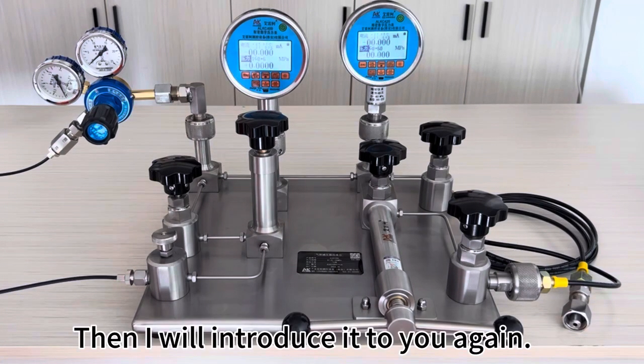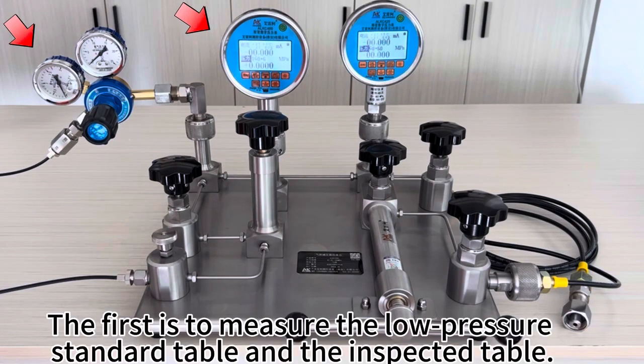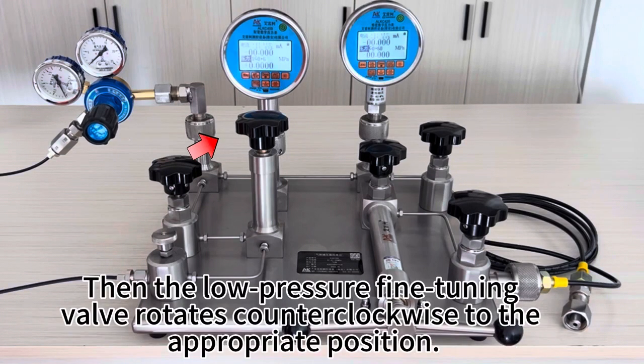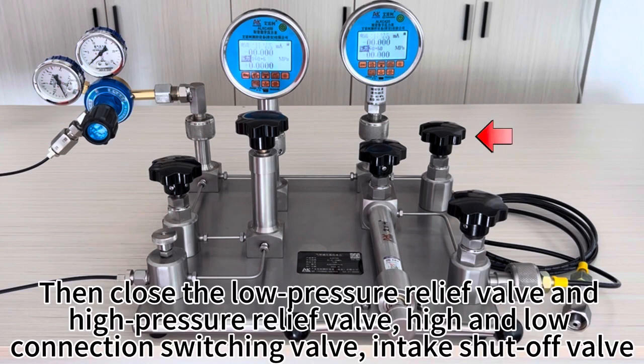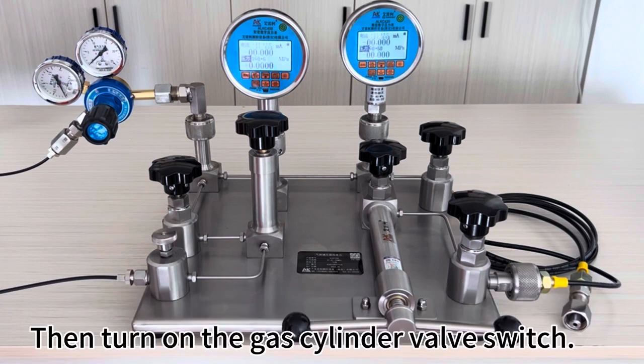Then I will introduce it to you again. The first is to measure the low pressure standard table and the inspected table. Then the low pressure fine-tuning valve rotates counterclockwise to the appropriate position. Then close the low pressure relief valve and high pressure relief valve, high and low connection switching valve, intake shut-off valve. Then turn on the gas cylinder valve switch.